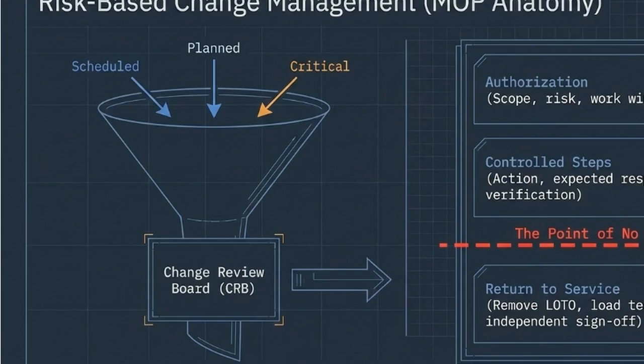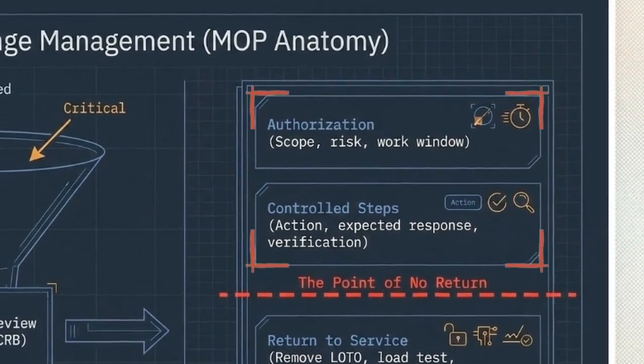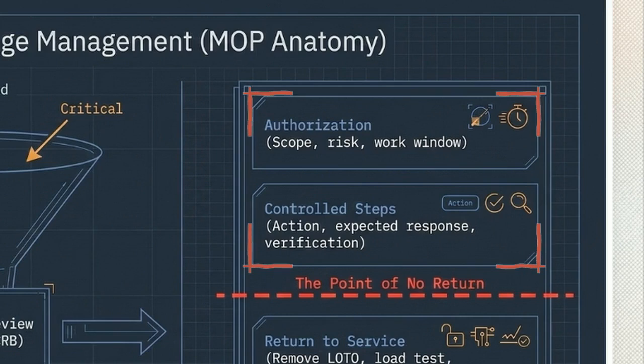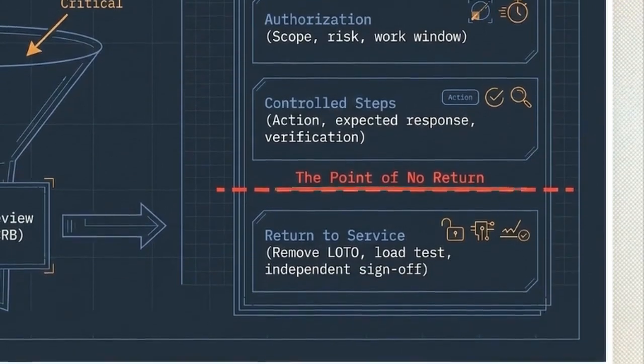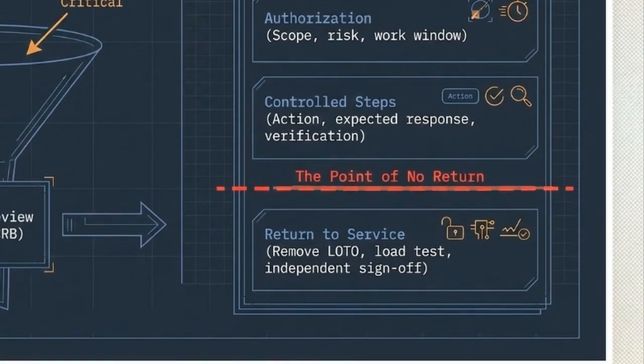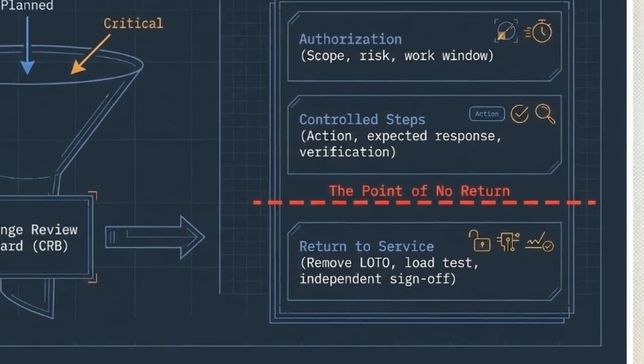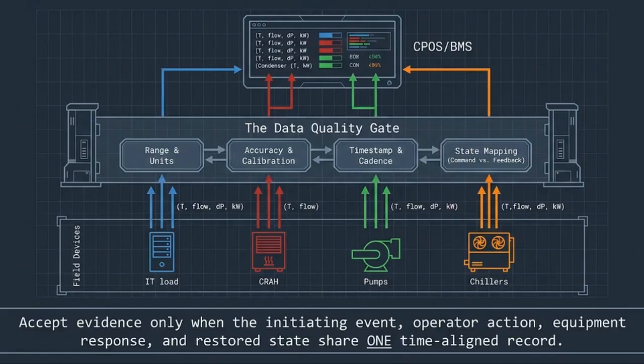This funnel diagram illustrates how methods of procedure pass through a risk-based change review board. Every planned action must outline authorization scope, controlled execution steps, and verification methods. Crucially, every procedure establishes a point of no return. If expected plant responses fail at or before this threshold, operators must execute a pre-verified rollback plan to restore the previous safe state.